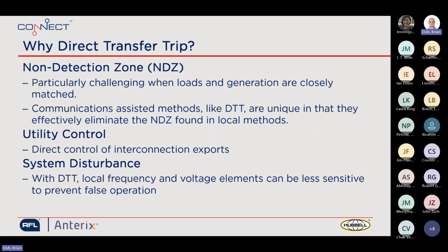So direct transfer trip is one of the most common communication assisted methods used for anti-islanding protection. And one of the main benefits of direct transfer trip is that you can eliminate what's called a non-detection zone that may be found in local type anti-islanding methods. So with a direct transfer trip system, you don't have a non-detection zone as long as you have a good communications channel. And another benefit is having utility control of the interconnection. So the utility can directly control the interconnection of the distributed generation.